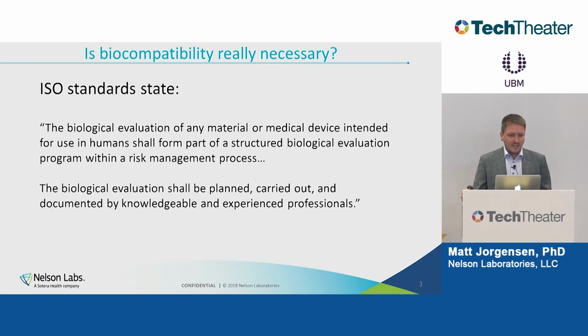The ISO standard states that the biological evaluation of any material or medical device intended for use in humans shall form part of a structured biological evaluation program within a risk management process. It also says that biological evaluation shall be planned, carried out, and documented by knowledgeable and experienced professionals. I've noticed that the FDA really looks for this, that whoever is doing the testing or planning the testing is truly knowledgeable and experienced and qualified to make that assessment.